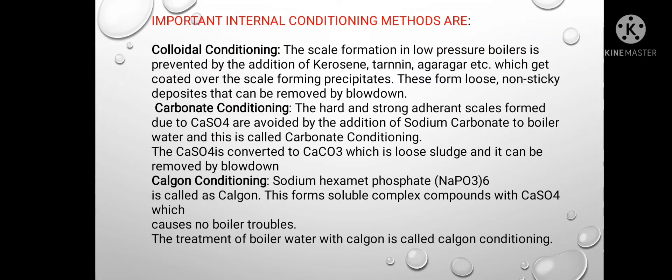Now we will see important internal conditioning methods. First, colloidal conditioning — scale formation in low-pressure boilers is prevented by the addition of kerosene, tannin, agar-agar, etc., which get coated over the scale-forming precipitates. These form loose, non-sticky deposits that can be removed by blow-down.